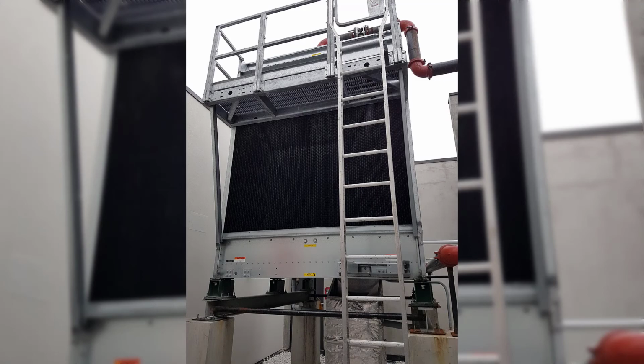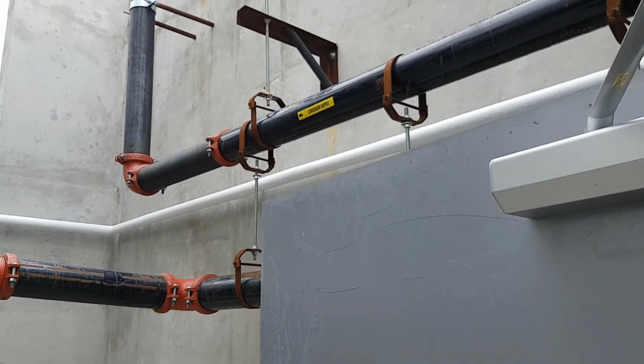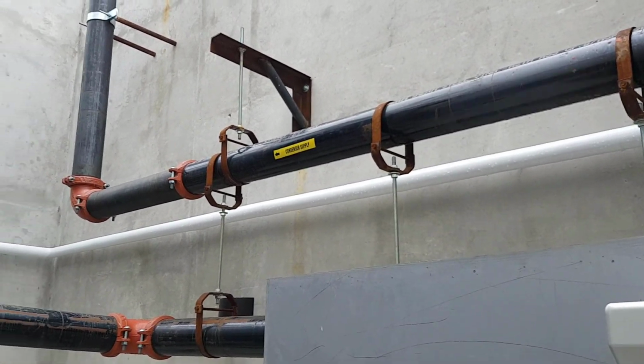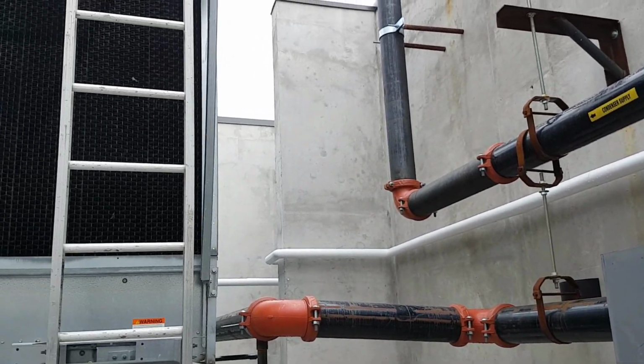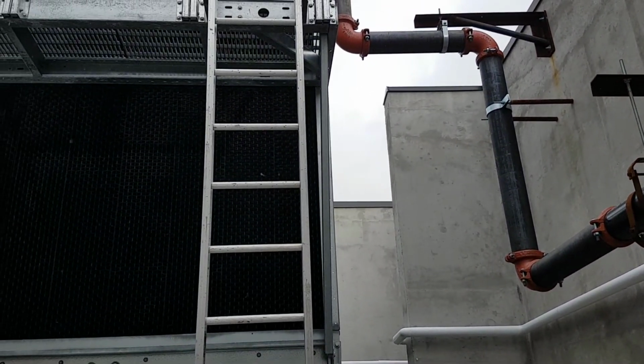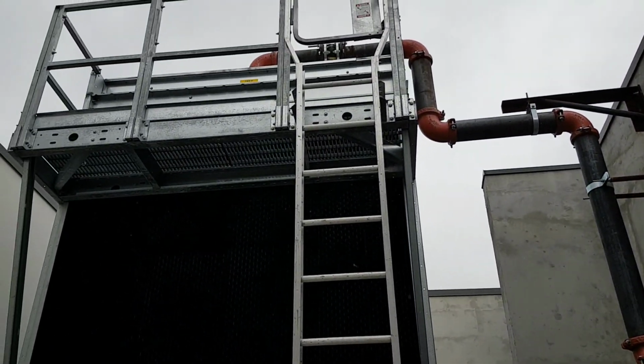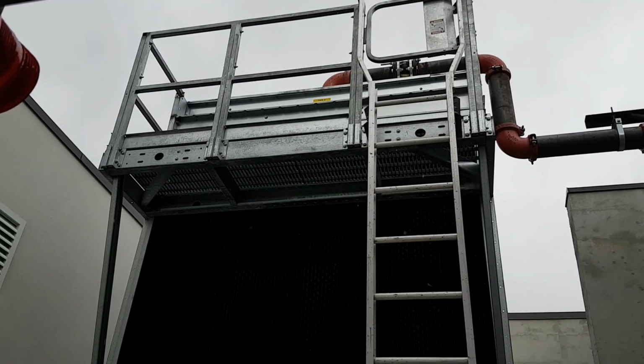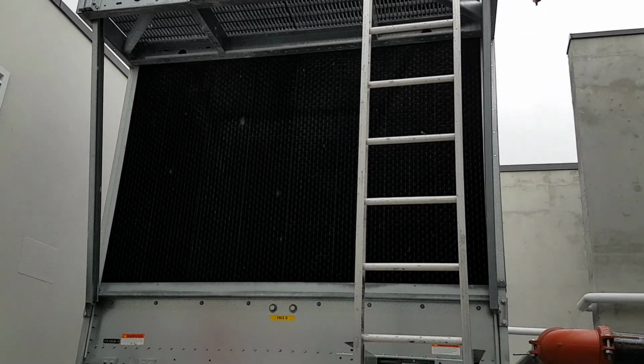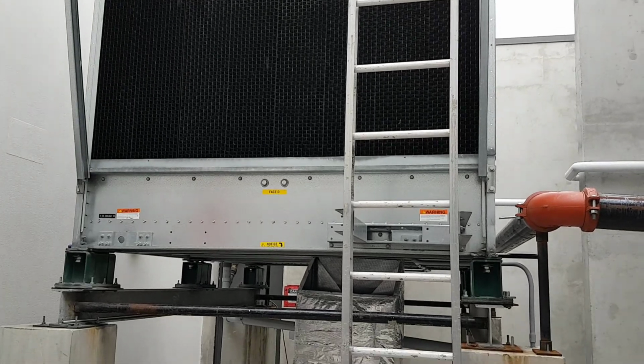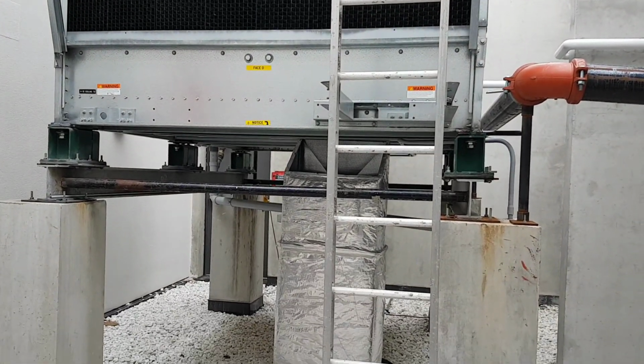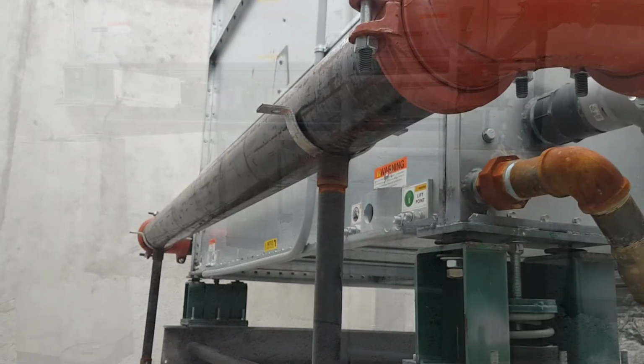cooling tower that's located just next to the chiller. Here are the condenser water pipes connecting the cooling tower to the chiller and pumps. The condenser water is pumped from the chiller room up and into the top of the tower, where you can just see an expansion joint at the top. The water falls through the tower while fans pull air across the water, cooling it down. The lower pipe brings water from the tower basin back to the pumps.